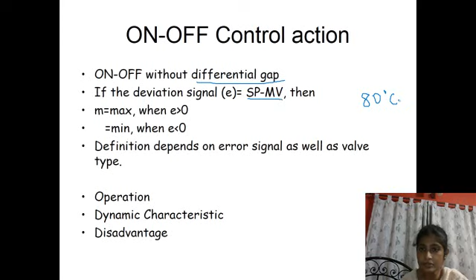That's why, for a real system, a differential gap is introduced. Differential gap means, instead of using 80 degrees centigrade, it should be treated as 80 degrees plus or minus, say, 2, 3 or 5 degrees centigrade. That means that is the band. So instead of operating at the particular value of 80, it should operate, say, at 82 at the upper limit and 78 at the lower limit, or if it is 3 degrees, say 80 minus 3 and 80 plus 3.